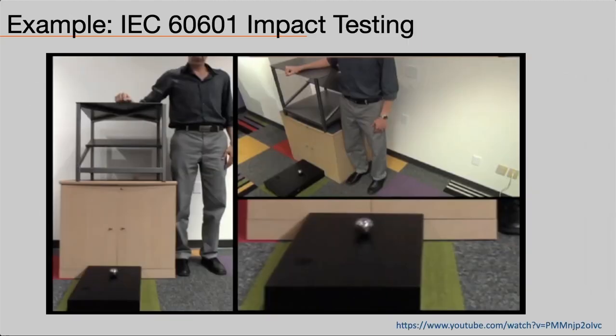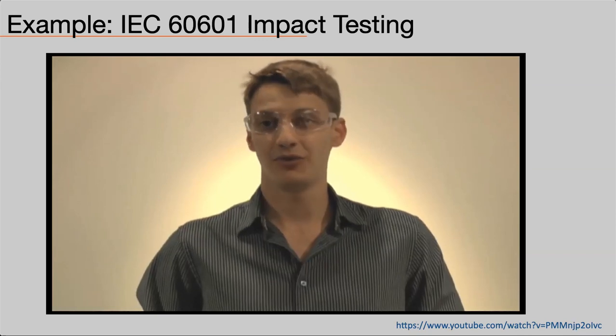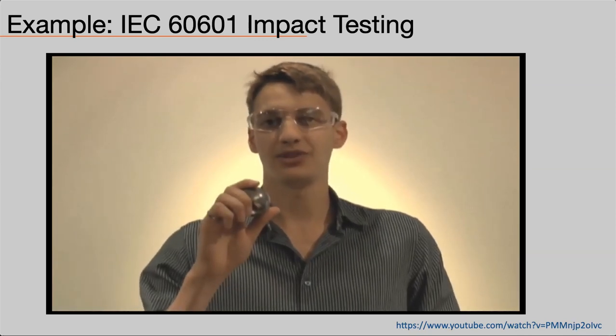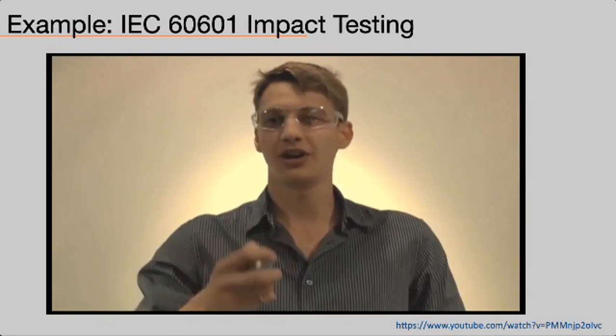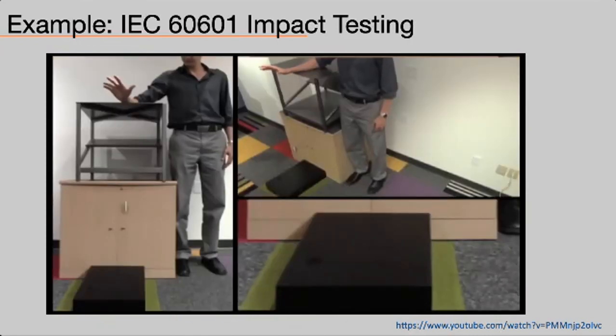Okay, here's an example of one of the tests medical devices have to pass under the IEC 60601 impact testing. Look at this video. To perform the test, simply drop a 500 gram steel ball from a height of 1.3 meters onto the top of your medical device.